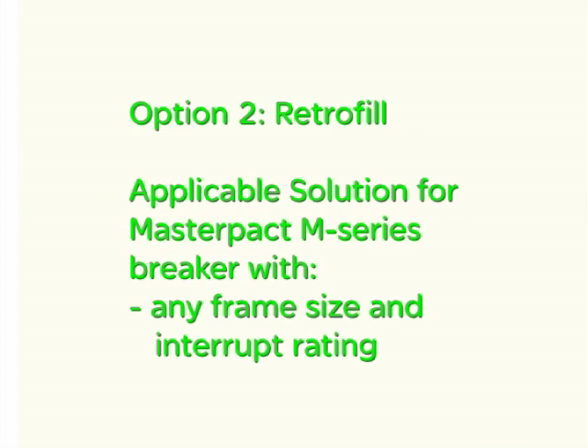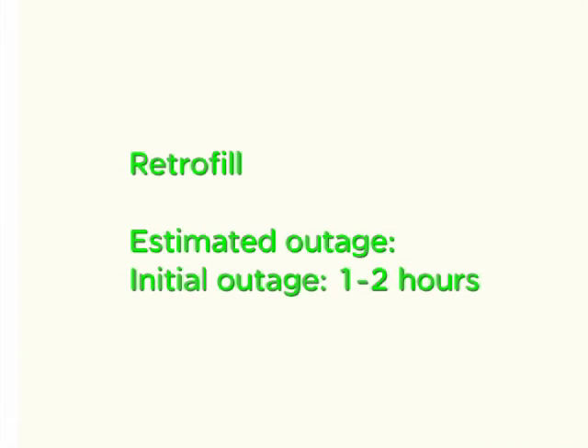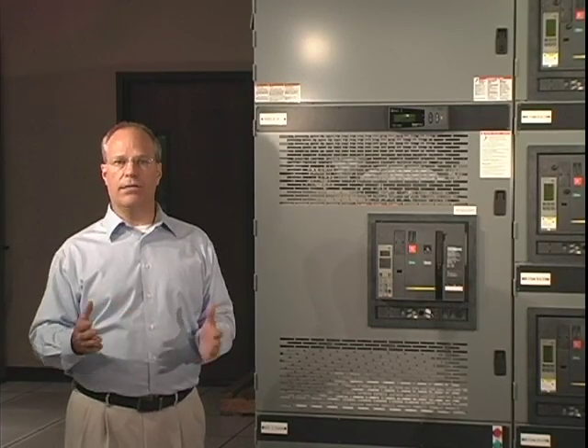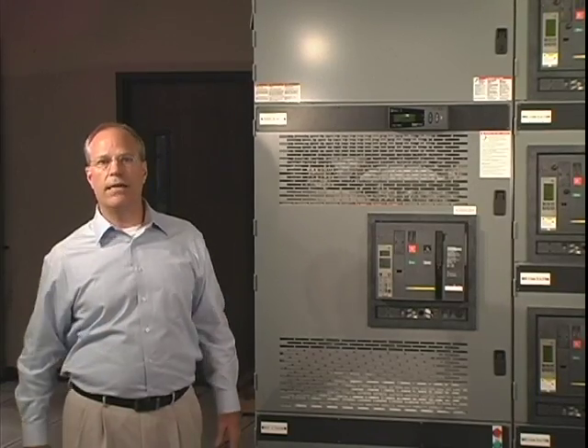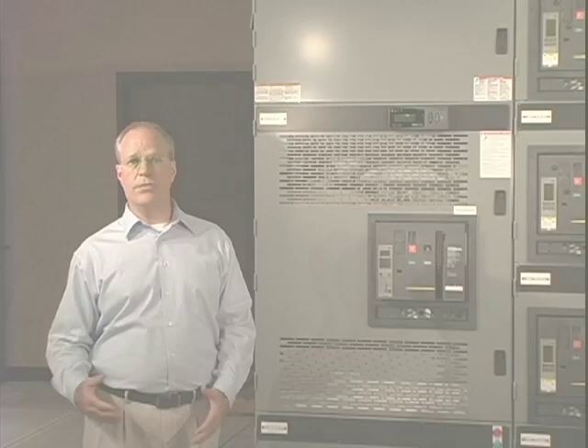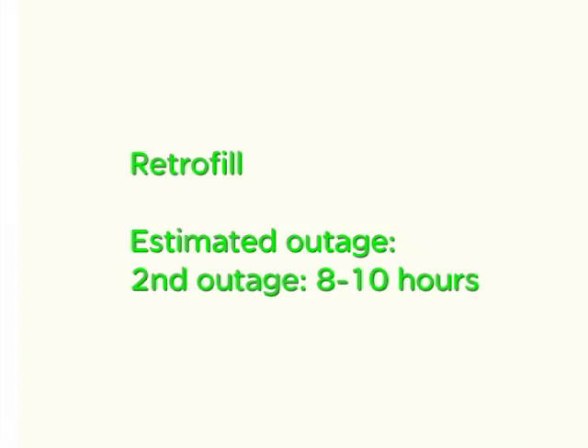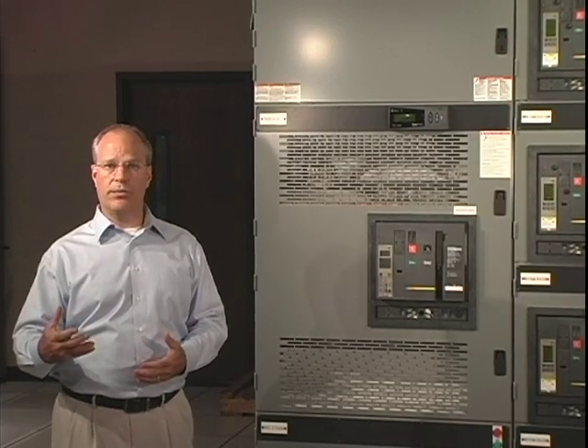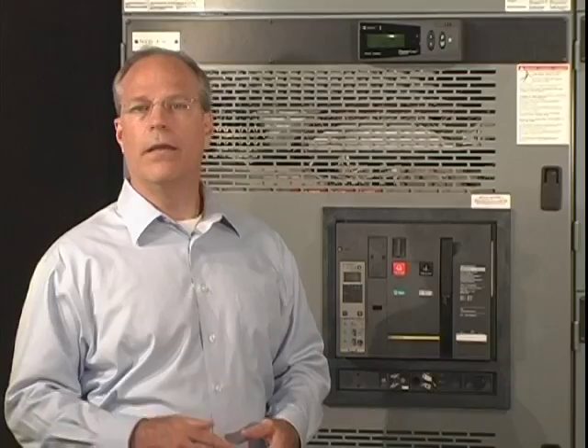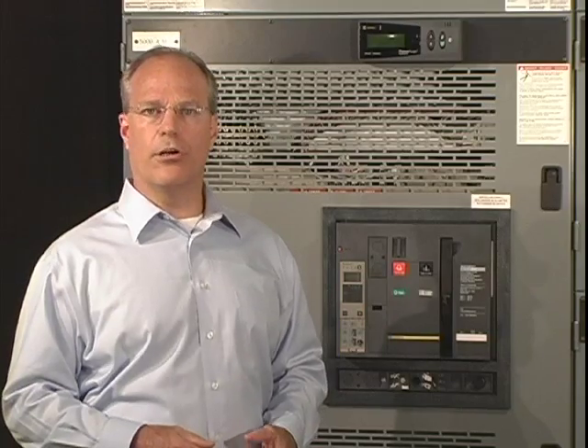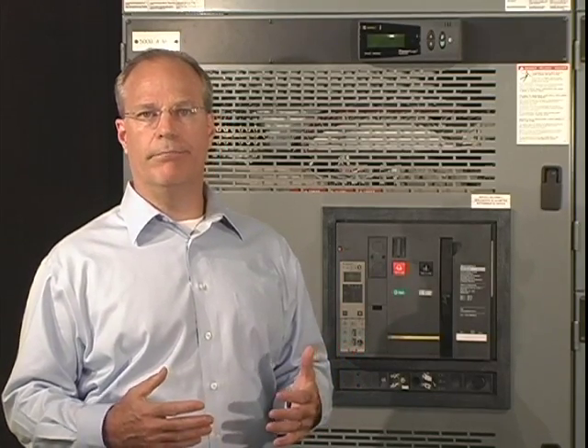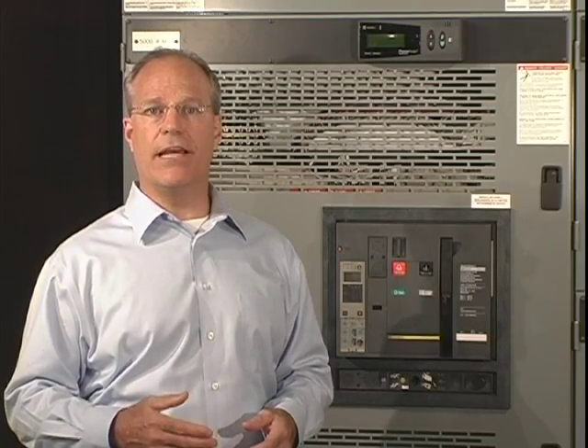The second option, applicable to M-Series breakers of all ratings, would be a retrofill. Schneider Electric will require an initial outage to obtain critical internal dimensions within the non-Schneider OEM switchgear structure. The Schneider Electric engineers then design and assemble a kit of components to facilitate the retrofill process. A more extensive outage is then coordinated to remove the old circuit breaker and the cradle, and the Schneider Electric field service representative then installs the new Masterpact NW cell adapters, cradle, and breaker. And the end user has a modern circuit breaker with enhanced features and, most importantly, peace of mind that the reliability of the system will remain intact for many, many years.